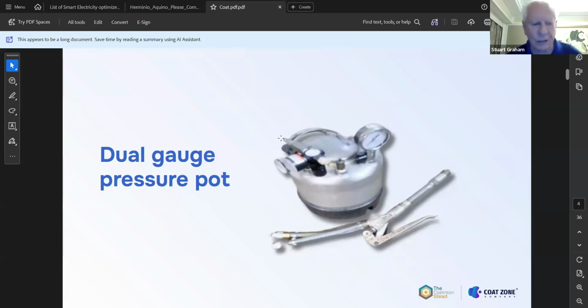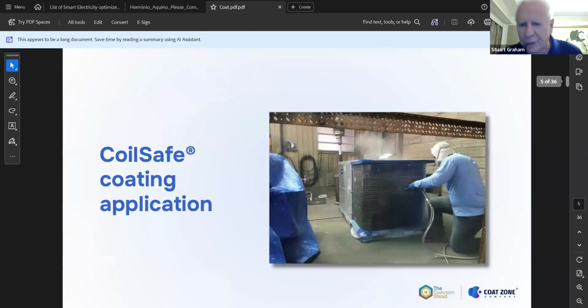This is what's needed if we're actually going to spray a coil of an air conditioning unit, which is the key component for heat transfer and efficiency of that unit. If we're only treating a solid surface, we can use a sponge brush to apply the product to protect against corrosion. We use the dual gauge pressure pot so we atomize the product so it comes out like a fog-like droplet. If you're trying to spray a coil 4 or 5 rows thick, a wet spray will never get through. So we atomize it, as you can see in this slide, where it comes out like a fog-like droplet on the far side. We're spraying from the outside in and the inside out, and that way we're able to encapsulate everything.